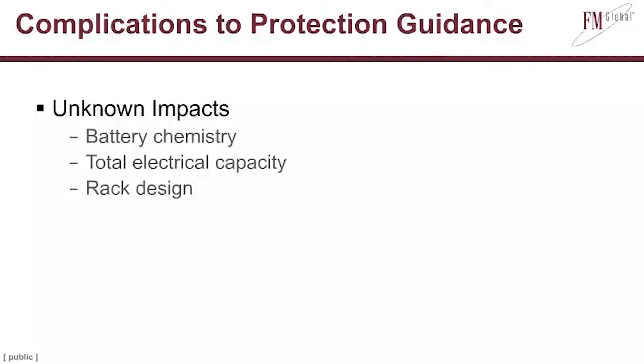The racks that I tested had five-sided metal with a bunch of modules inside. There was no specific metal door on these. And so the fires came out the face, and we saw the fires exit, and eventually you could put a fire hose and spray water right onto the rack. Well, consider now putting a metal face, a metal door, onto that. Now the fire can't get out the face, meaning the heating condition within the rack completely changes.